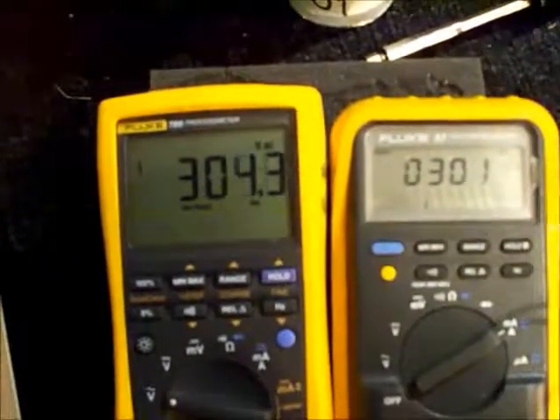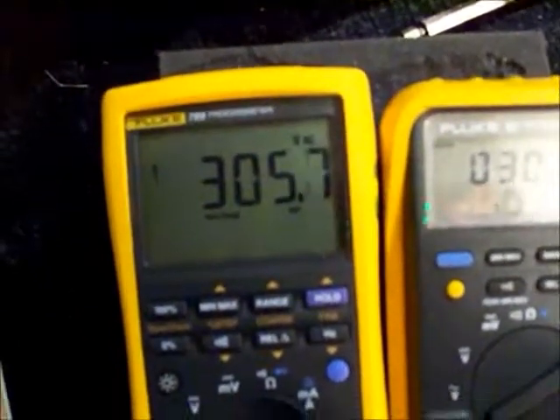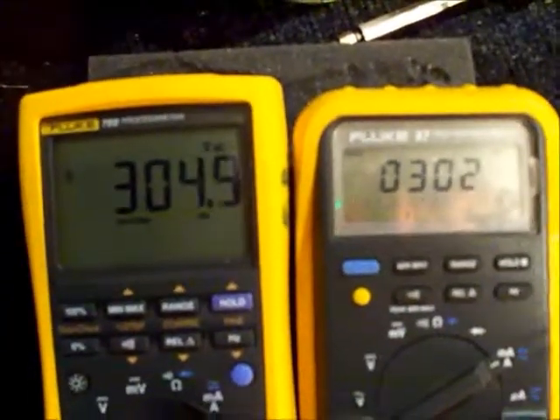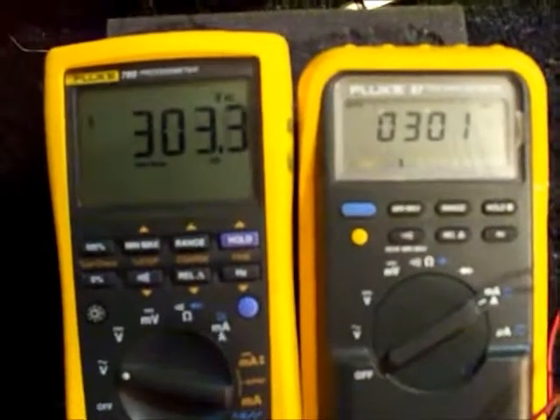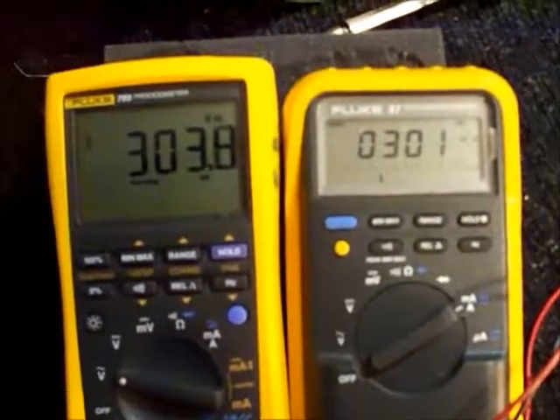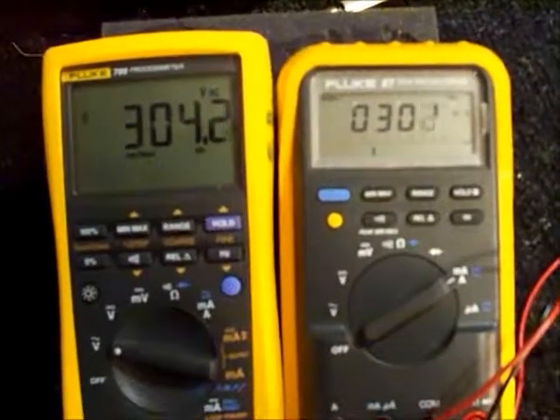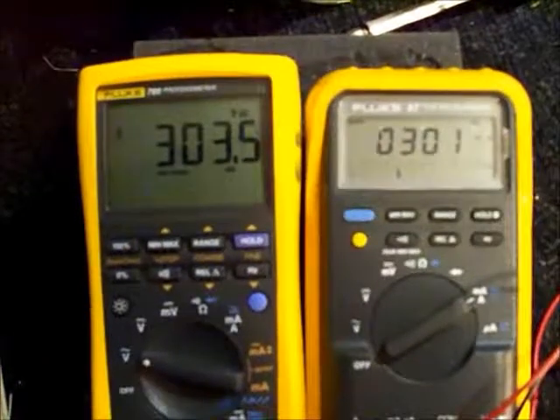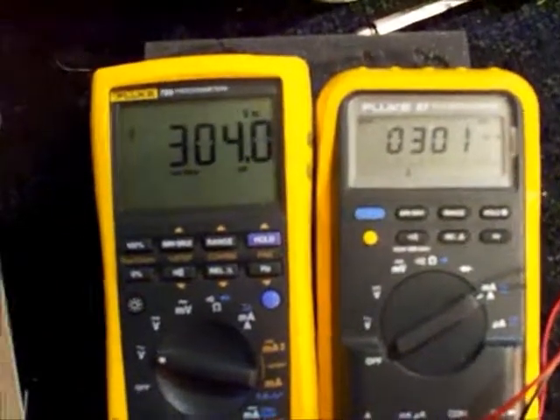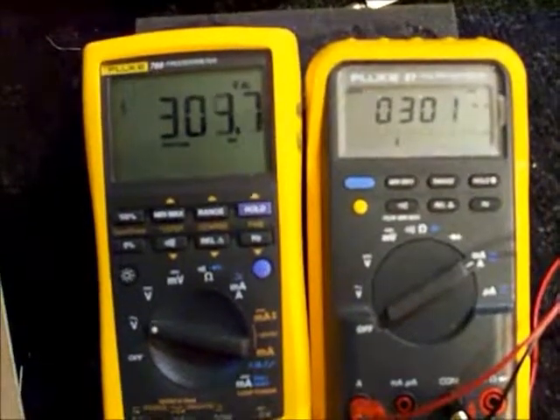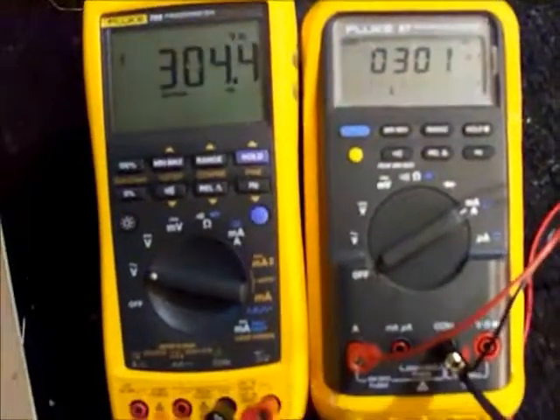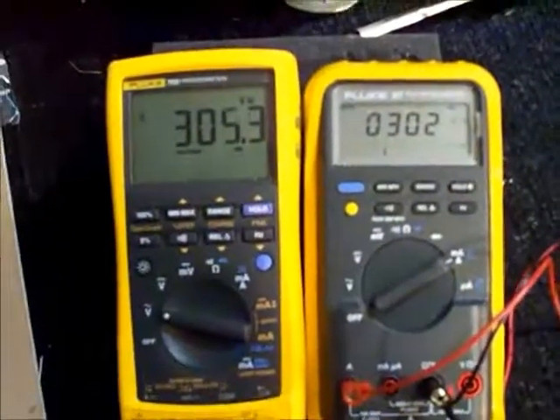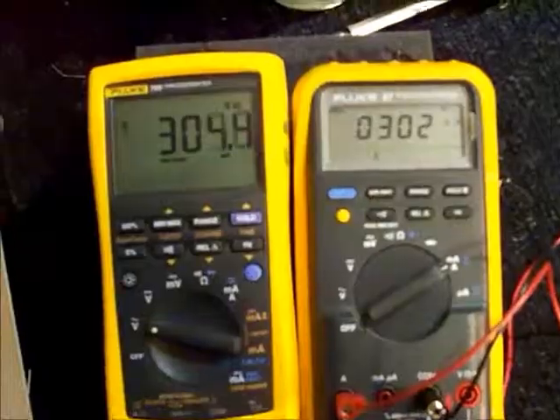Let's see what happens when we turn it on. There you have it, that's 300 volts AC, 305, and the current draw is 300 milliamps. No problem. So I guess we're going to have to go back to the drawing board on this and try to figure out what's going on, why this thing is dipping on its voltage. But according to the nameplate on the transformer, this is what it's supposed to be doing, and that's exactly what it's doing. Alright, we'll be back.